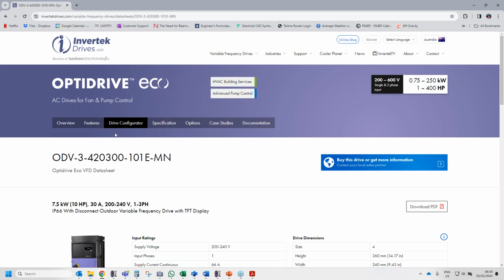Okay. What are the benefits of the EMC filter? Well, the EMC filter is just there to stop electrical noise, because any drive on the market, any VFD on the market, switches semiconductors, so it causes electrical noise. You need a filter there to stop any drive interfering with other electrical equipment in the system.